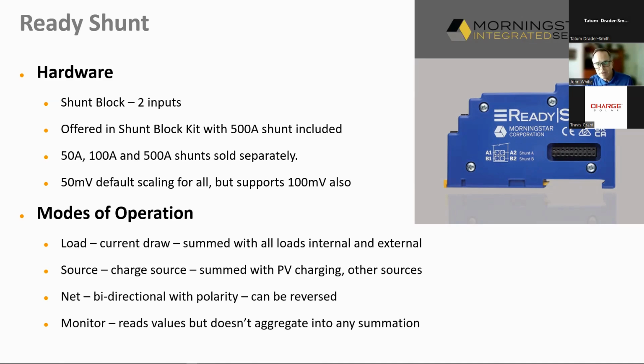And the modes of operation are load, source, net, and monitoring. From a current draw standpoint, this is important for summing all the different loads, both internal and external to the system. For charging source, it'll sum with PV charging and other external sources, so if you've got generators or fuel cells, things like that, we can connect those in.